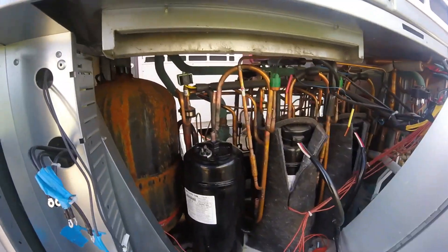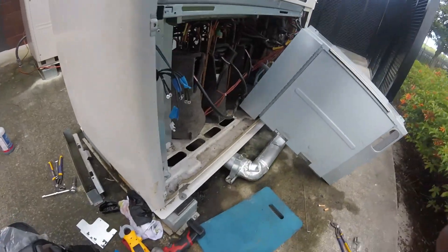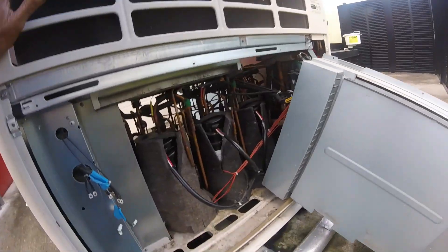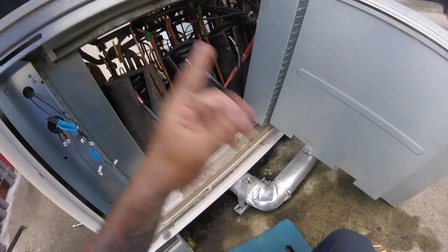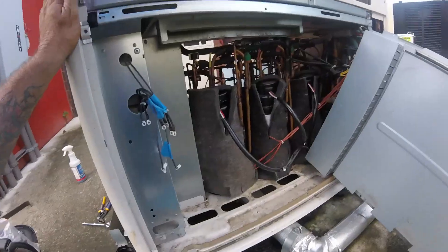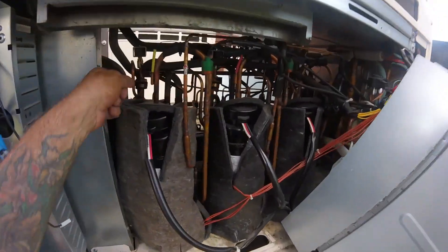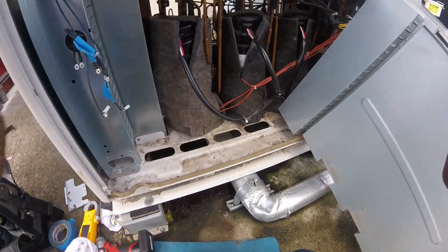We're getting there - got the new compressor ready, pressure tested everything, right now in a vacuum. We're back together. I've got to put this back, wire it up, and I've got to change the board. It's so hot I had to get a fan going. That weld in the back was not easy - just trying to pop it free.